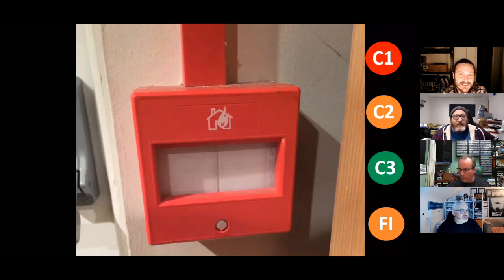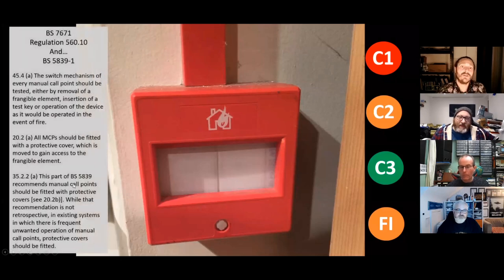I mean, something I can see in the image is this is right next to a fire door. Yeah. So this is the point of exit of the building. It looks like it. So this kind of call point really should have no ambiguity about how it's used. Yeah. Because to me, that increases the risk a little bit. People are going to aim for this door. You want that call point there to operate and not be hard to interpret. Other call points that people may pass, if they're going to a funnel position of an escape door, that last call point must not be confusing.